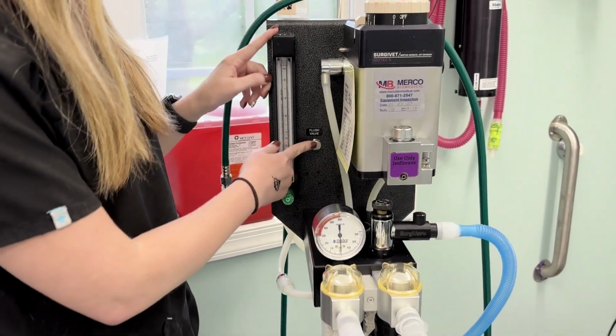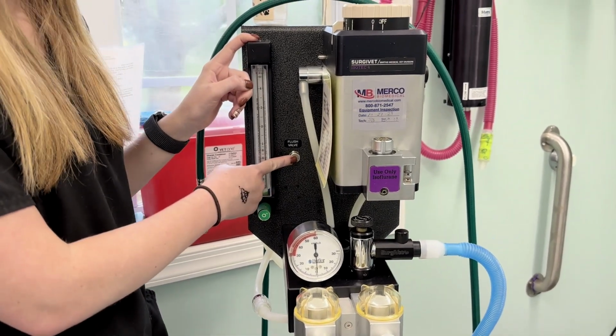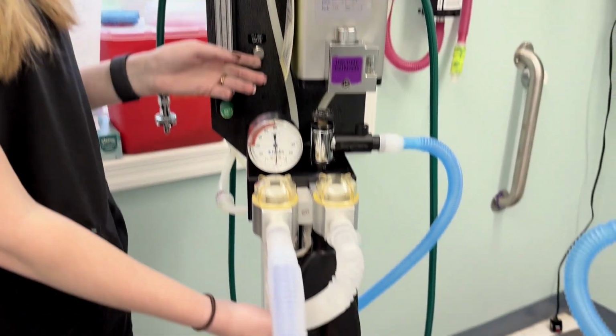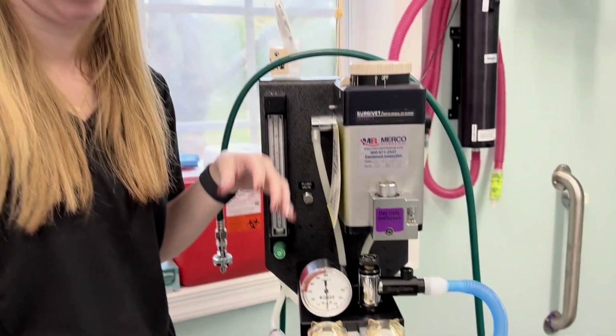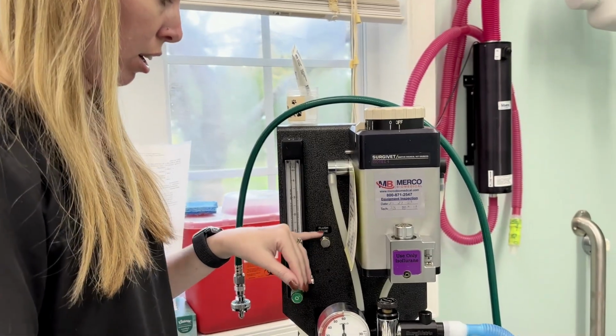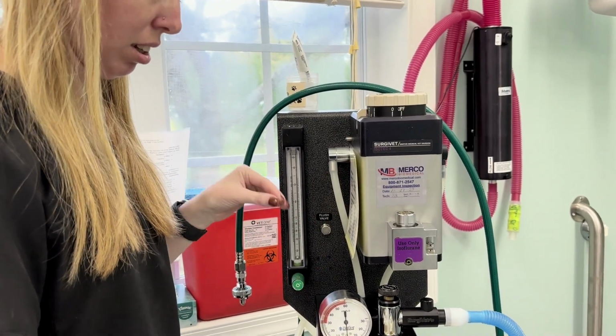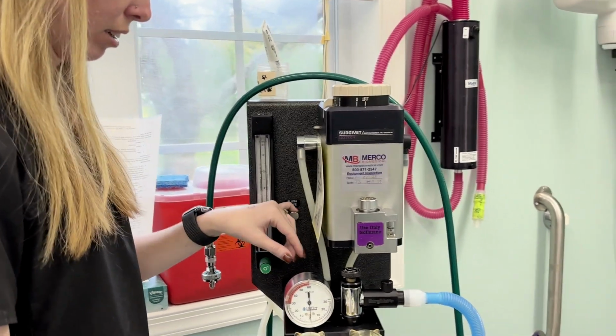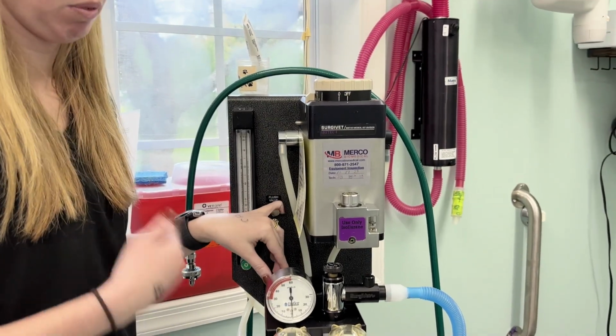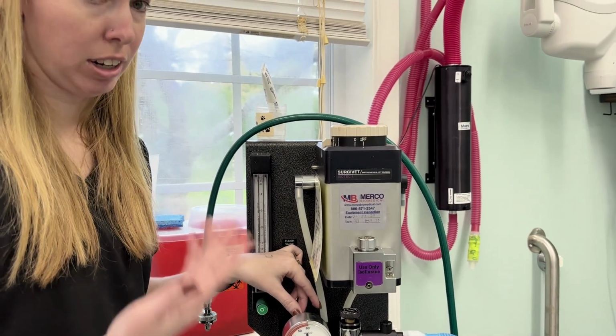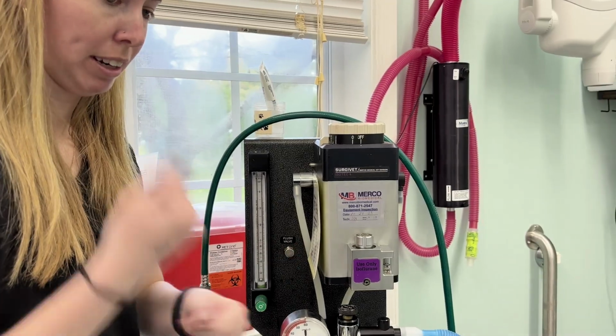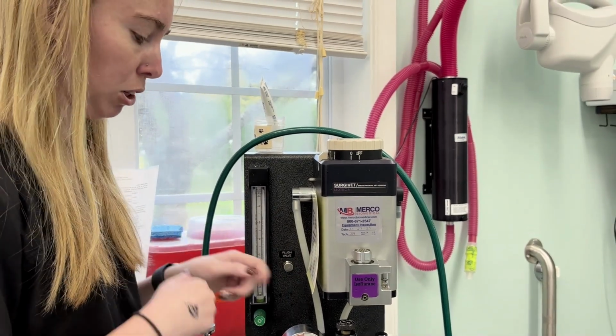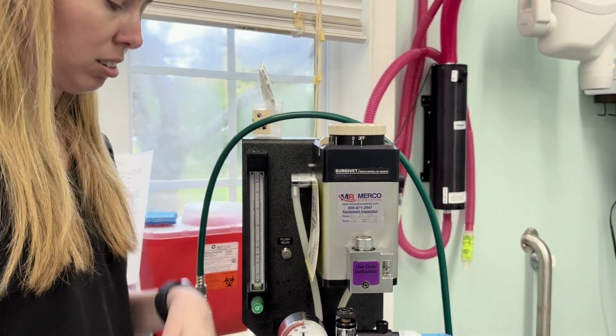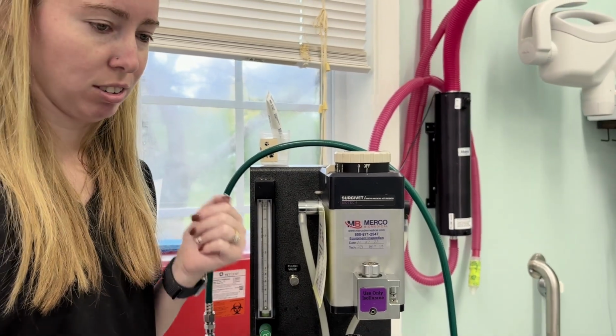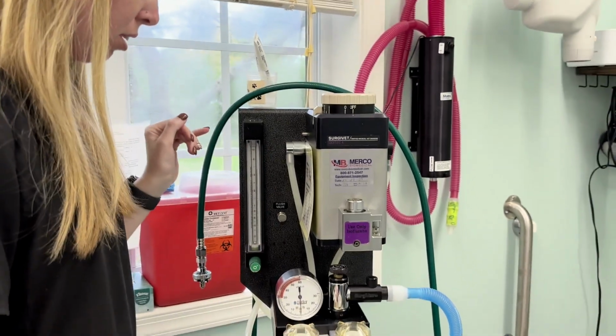And then right next to it is the flush valve. This is used to fill up the reservoir bag, and this flushes 100% oxygen into the patient. This is also used when you're leak testing the machine as well. You can get rid of your anesthetic gases after anesthesia by unattaching the patient from the machine, flushing it, getting rid of all those gases, and then putting it back on the patient.